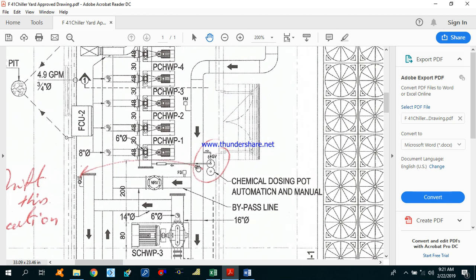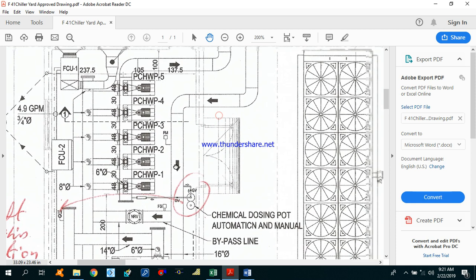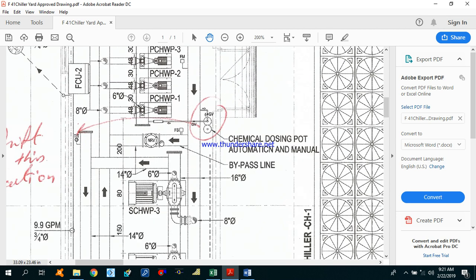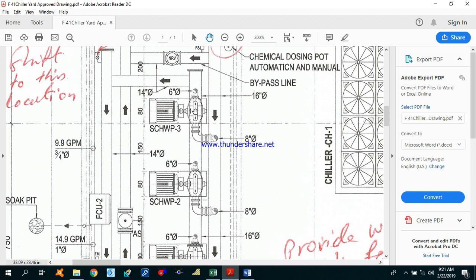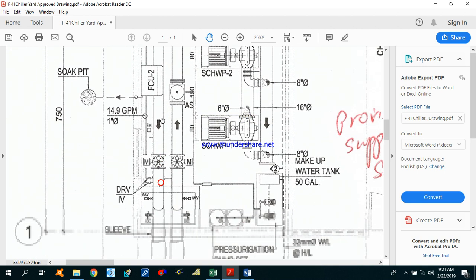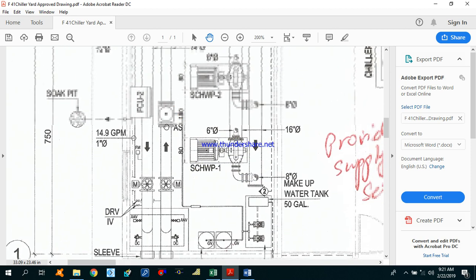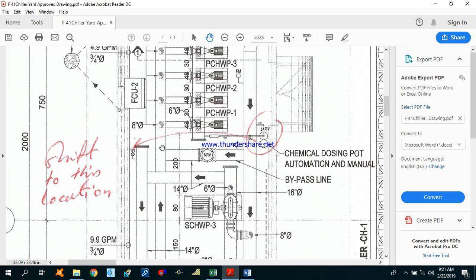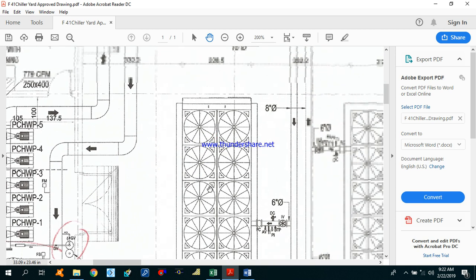We are using automatic and manual chemical dosing pots here. These dosing pots with the dosing pumps are used to supply a predetermined quantity of chemicals at regular intervals. This is how the chemical dosing pot is connected with the chilled water lines. This is our chilled water supply line coming from the chillers, and this is our bypass line. The chilled water supplies from the chillers into the secondary chilled water pumps — there are three — then supplies to the buildings, and returns through the primary chilled water pumps back to the chillers. The whole process repeats.